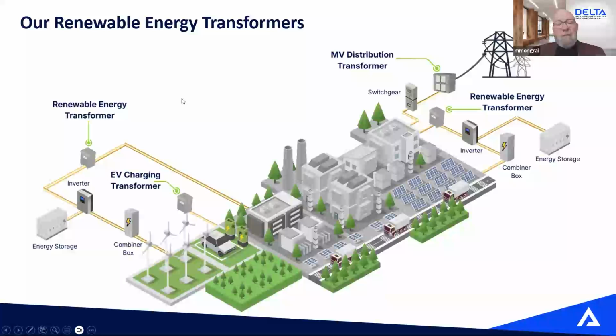Why is it important when you deal with a bidirectional transformer? First of all, it's what we call the inrush. When the transformer is sitting unenergized and you energize it, there's a phenomenon called inrush to create this magnetic field in the core so that the primary and the secondary windings can work, if I could say. In the first 10 cycles, you're going to have this massive demand of energy to magnetize the core. The core is like a sponge. It's going to need lots of energy to get magnetized. So that peak of inrush can sometimes be 10 to 15 times the nominal current. It's a very short peak, 10 cycles, so it's probably 1/10 of a second, but still.